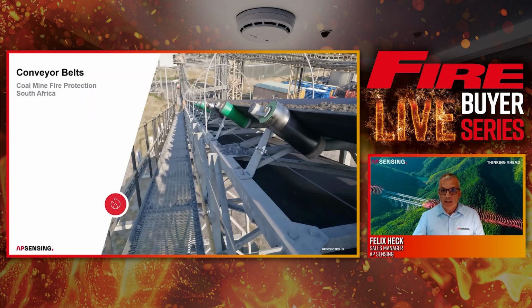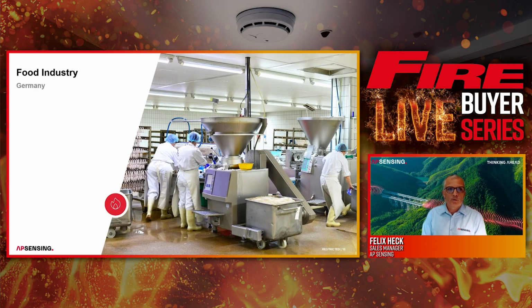From very dirty, dusty coal mines in South Africa to German food industry. Here, for example, it is not the dust and the dirt, it is more the cleaning process that is really a challenge for this environment. We have a very, very high humidity, sometimes with chemicals and so on, different temperature zones. So in the production is a different temperature than in the cooking area or in the deep freeze area. So this is something that we have to deal with in terms of fire protection, and our linear heat detection systems can really be a very good solution here.